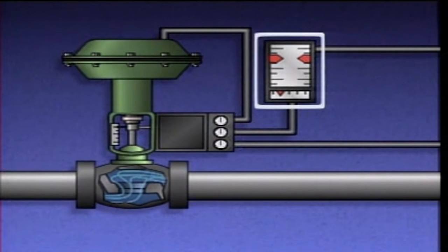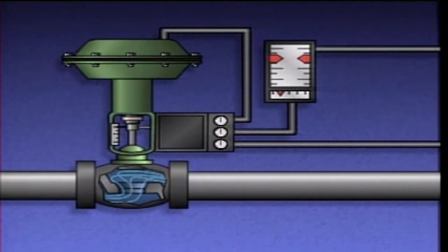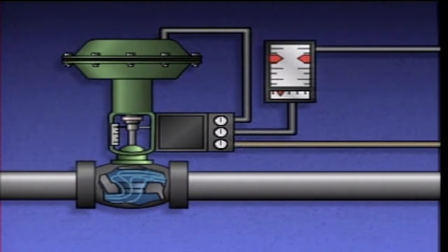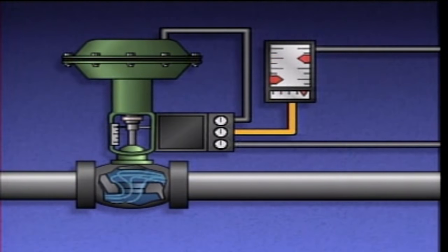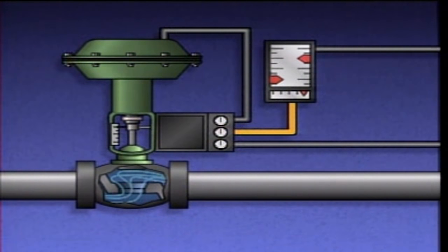When a positioner is used with an actuator, the signal from the controller goes to the positioner instead of directly to the actuator. The positioner controls a source of air that is sent to the actuator. When the controller sends a signal to close the valve, the positioner receives the signal and converts it to the appropriate air pressure using its air supply.